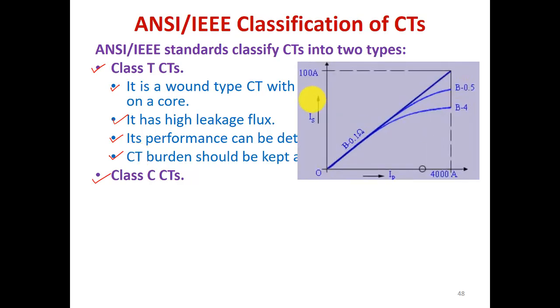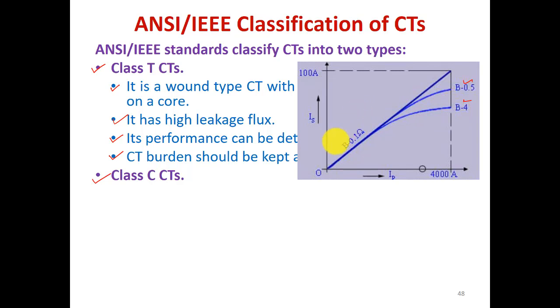The typical magnetizing characteristics of Class T CTs show a plot of Is versus Ip. The characteristics are plotted for three values of B: B = 0.1, B = 0.5, and B = 4. For B = 4 the CT is more saturated. Therefore it is always recommended that the performance of Class T CTs be determined based on test.